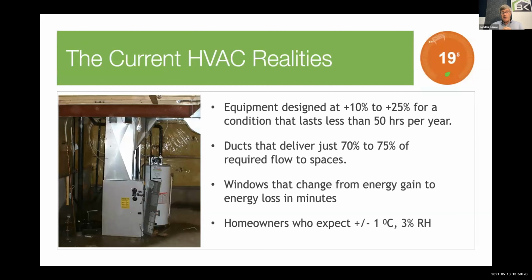The current HVAC realities are we design equipment 10 to 25% bigger than a condition that lasts 1% of the year or 0.4% of the year, 50 hours a year. And yet homeowners want it to be comfortable every day, not just on the coldest day. And we have ductwork that still leaks at the rate of 25%. Well, 20 to 25%. I should update this slide, at least in Ontario. In Alberta, unless you're sealing ductwork, your ducts are leaking at 25 to 30. In Ontario, let's be really clear, your ducts are leaking at 15 to 20, some of them 25.